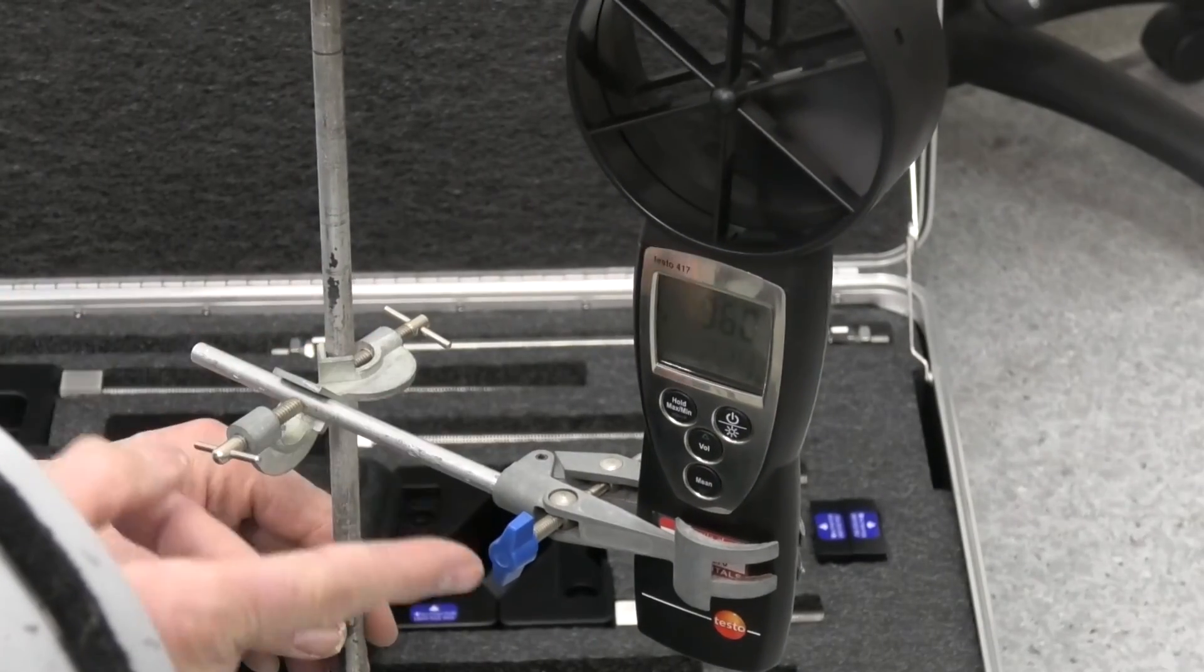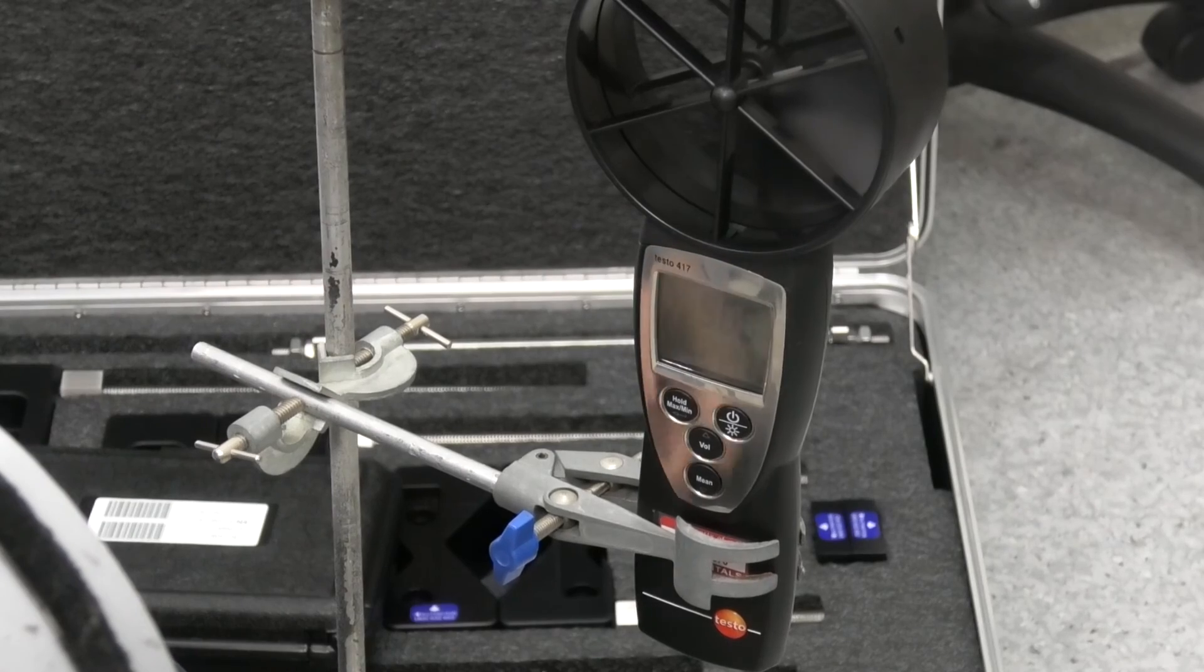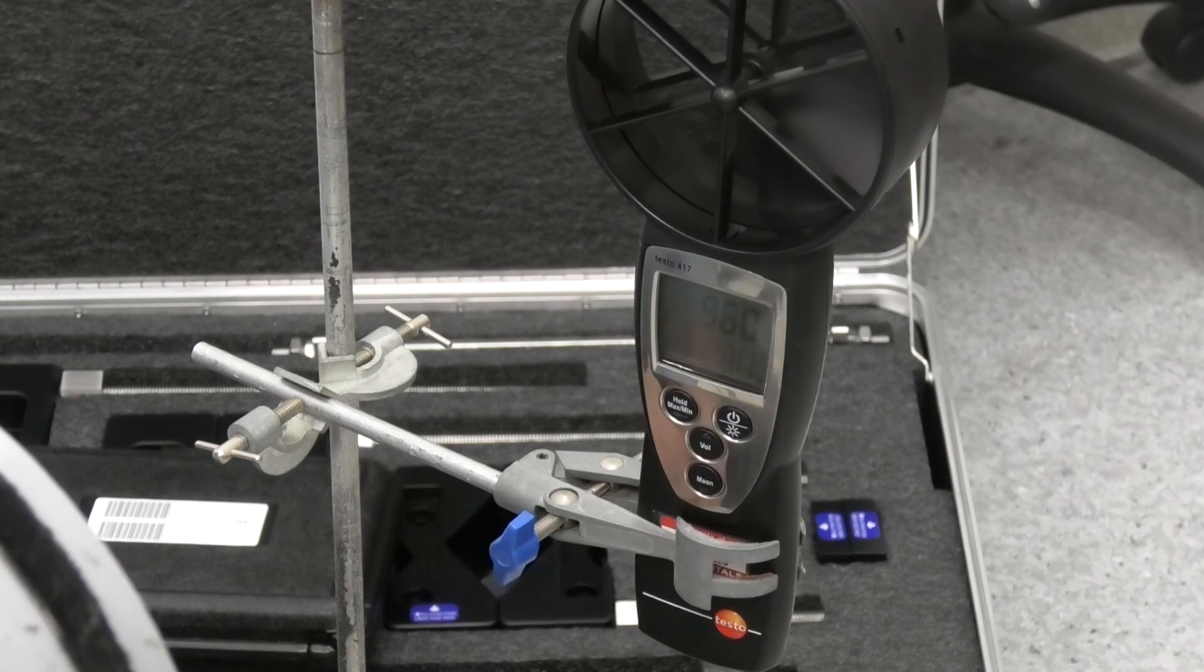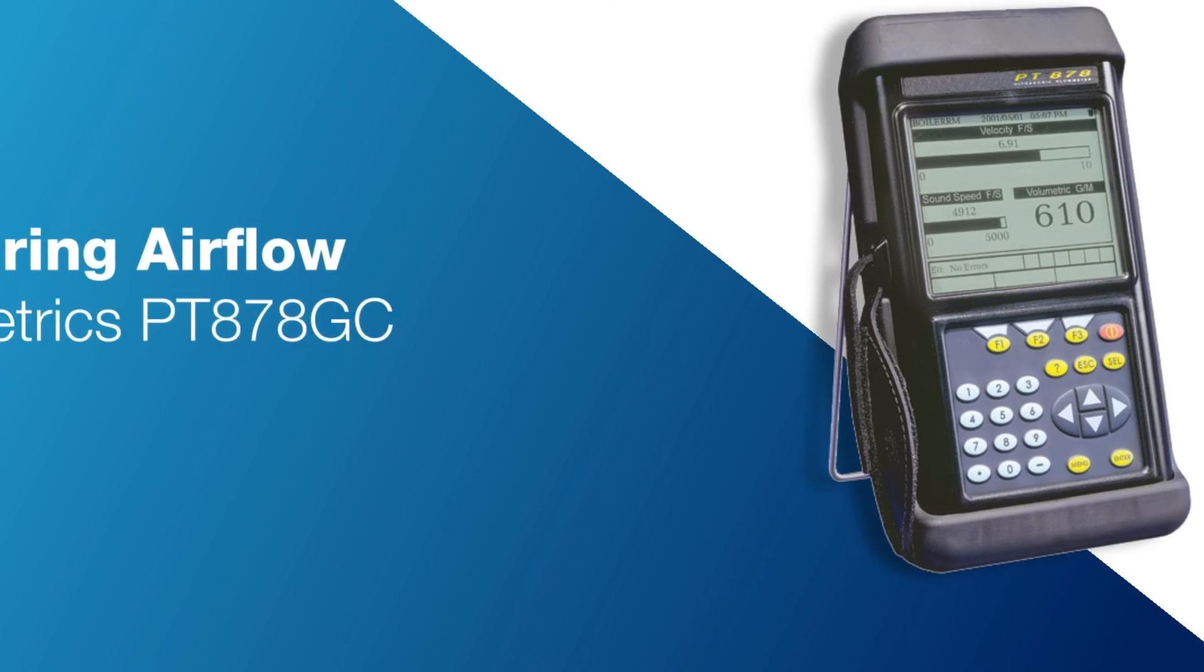Okay. This is the air velocity metre we've got at the end. And we're reading 9.5, 9.6. So all the measurements sort of correlate pretty well. Because it's not a particularly easy measurement to make. You've got to be very careful about instrument placement.